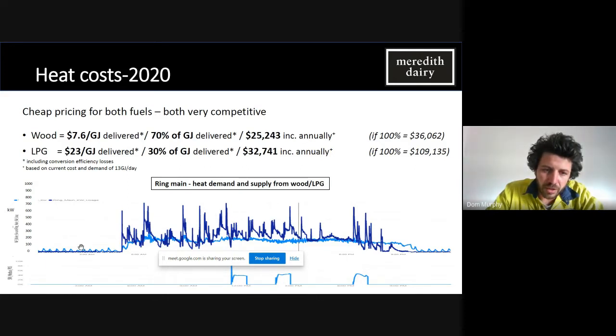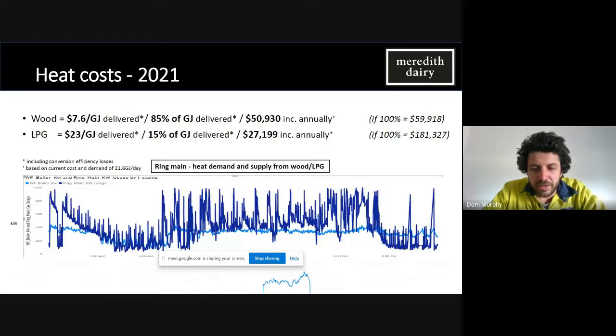You'll see another graph here. This is over a 24-hour period. You'll see essentially no demand and no heat from the boiler first thing in the morning until production starts, and then it tapers off overnight. That signaled that our buffer tank was recovered. The system was completely heated, and we had no ability to put heat anywhere, so the boiler had to dial itself down. So what we undertook was a process of saying, how can we shift that load to essentially create a thermal battery? And that's where we are in 2021.